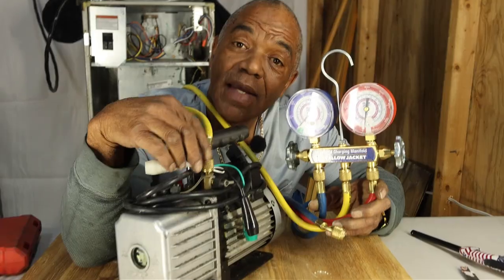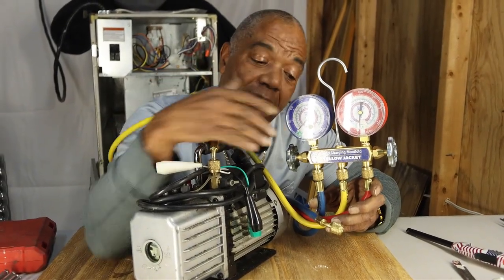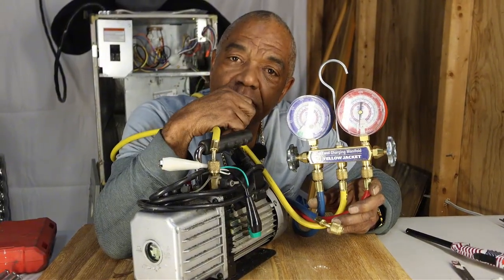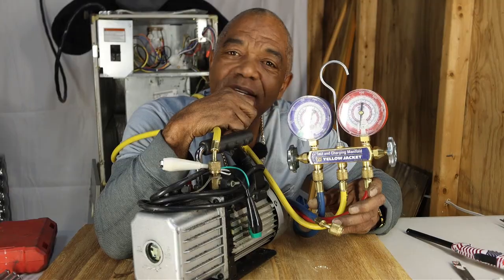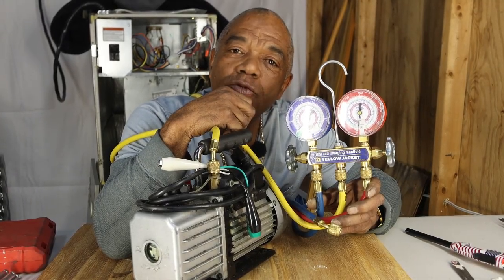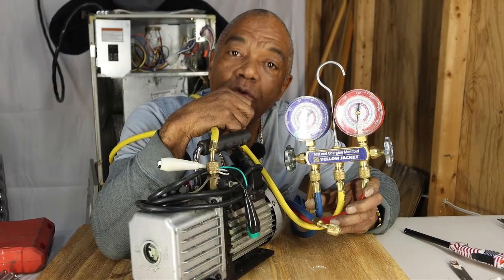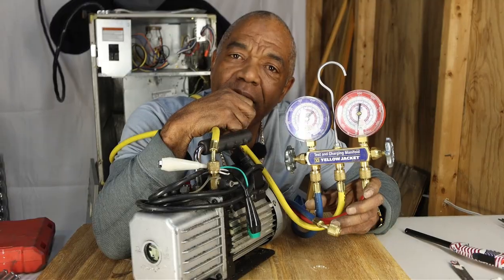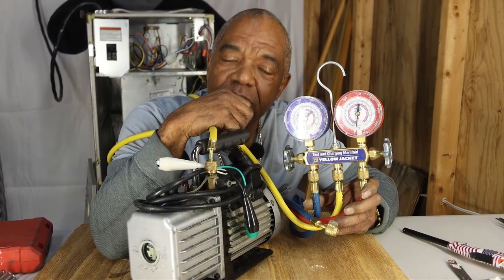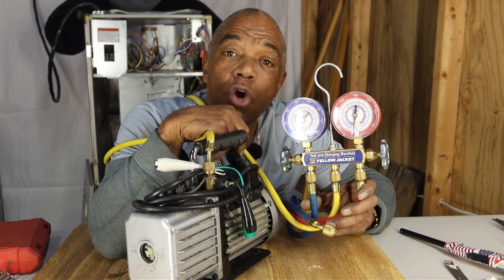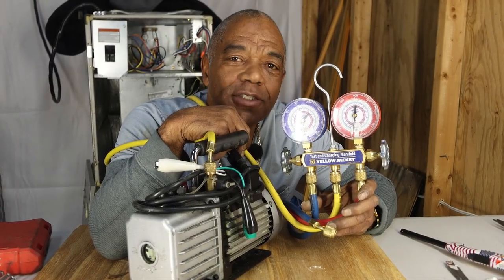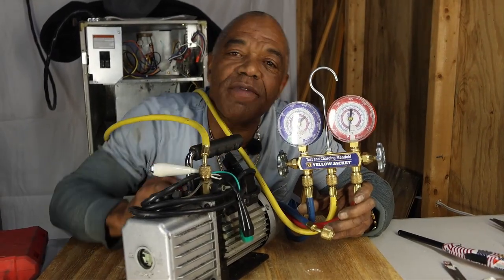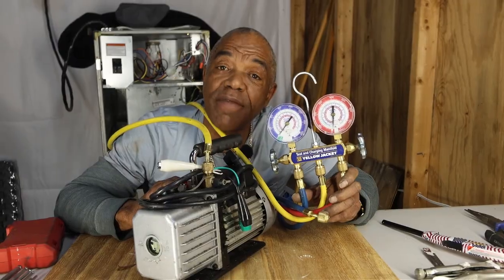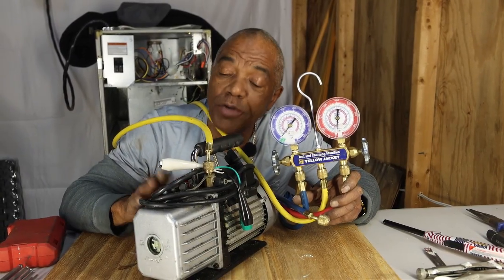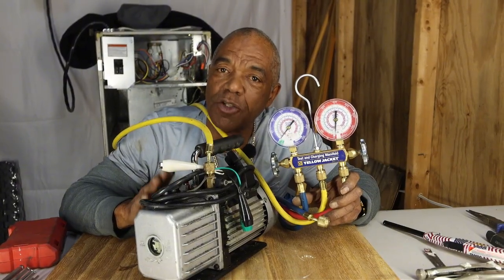But this pump can come on, it can run, and if you feel the hose, you feel the suction, but the vacuum pump isn't any good because it will not reach the negative micron level that you need. A lot of individuals sell vacuum pumps to pawn stores when they no longer work, but they still run. And the attendant at the pawn shop doesn't know how to determine whether that's a good vacuum pump or not. So don't ever buy a vacuum pump from a pawn shop. Although they're expensive, you must buy it new.